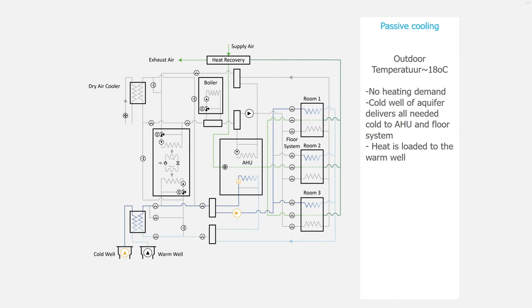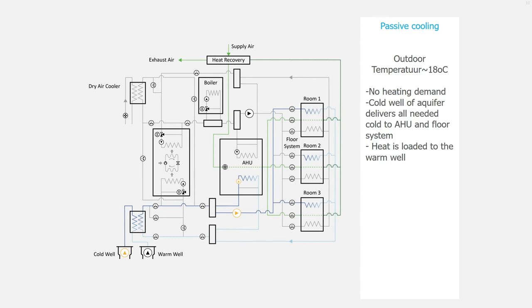Let's go further. What we call passive cooling. The outdoor temperature is now around 18 degrees Celsius. There is no heating demand but the cooling demand is higher. The cold well of the aquifer delivers all needed cold to the air handling unit and the floor system.